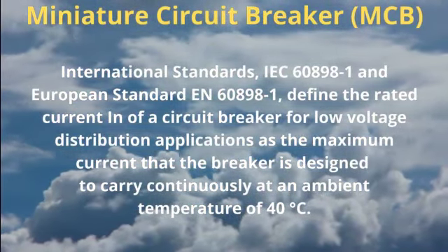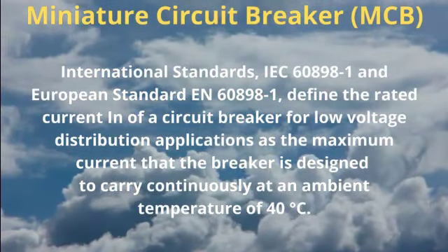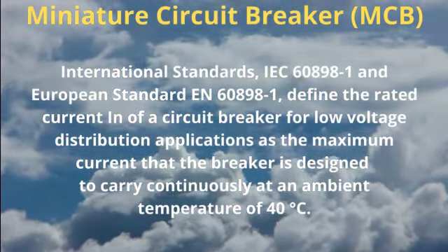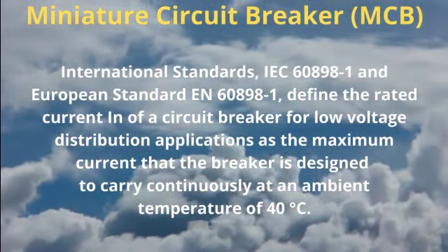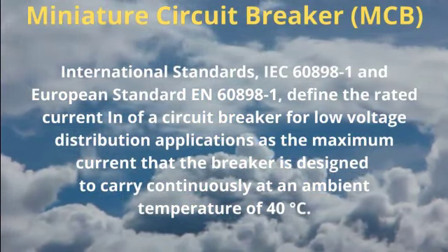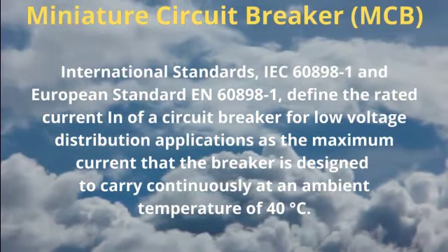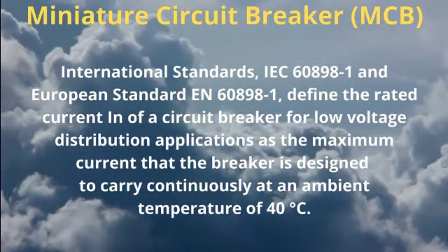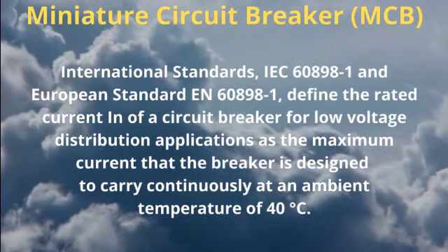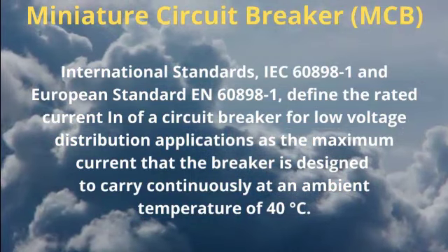International standard IEC 60898-1 and European standard EN 60898-1 define the rated current In of a circuit breaker for low voltage distribution applications as the maximum current that the breaker is designed to carry continuously at an ambient temperature of 40 degrees C.